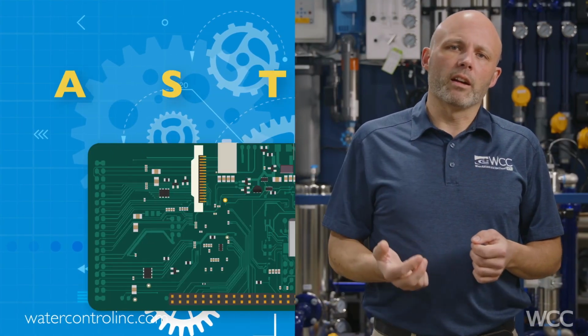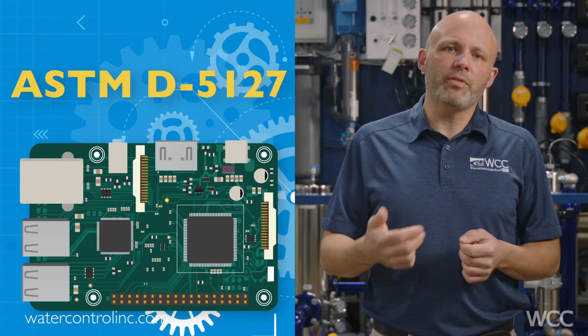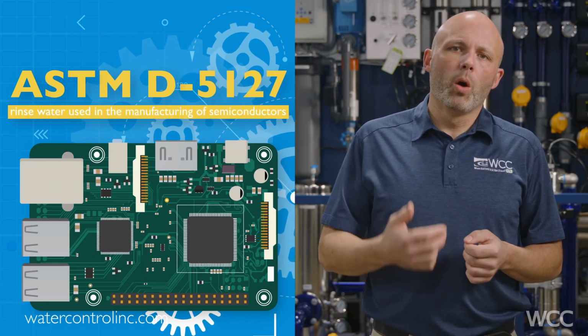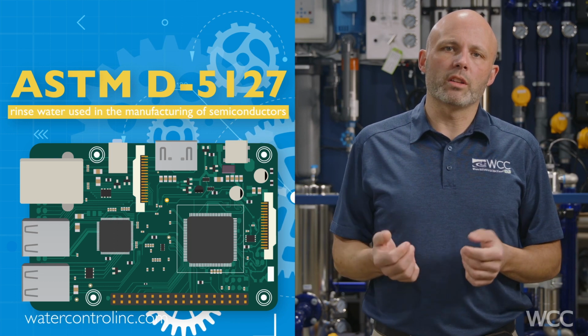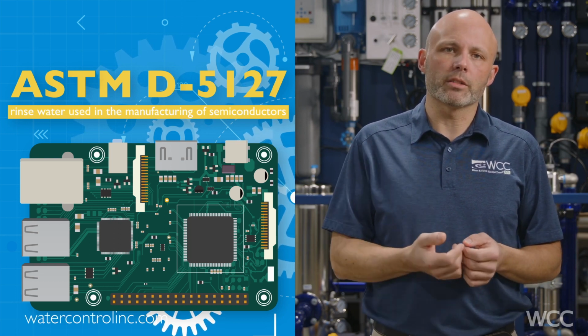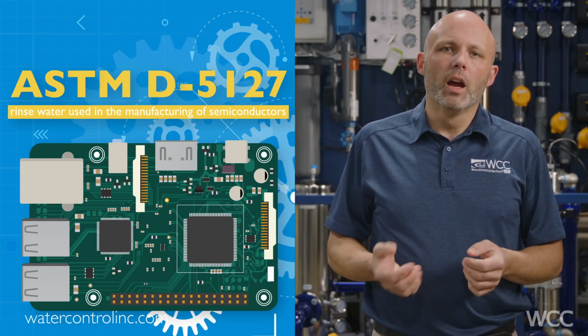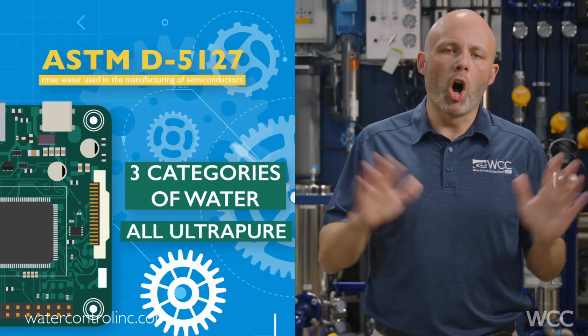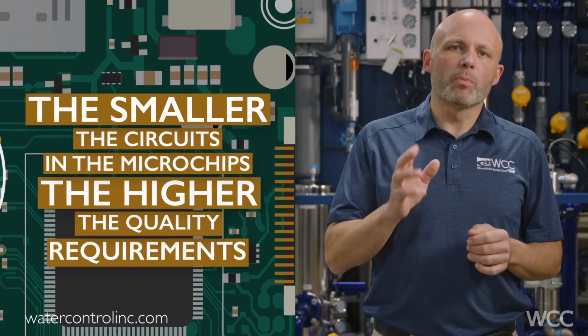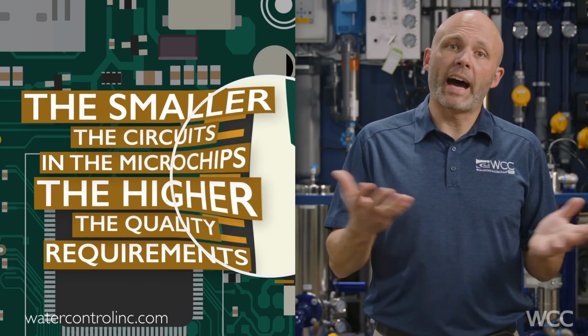The second standard I'll mention is ASTM D5127, which is specific to rinse water used in the manufacturing of semiconductors. We're talking microchips. There are 3 categories of water, all ultra-pure. The smaller the circuits in the microchips, the higher the quality requirements.